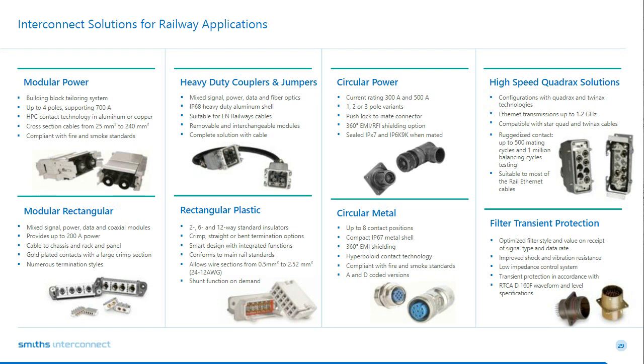Typically, why is it important to design a connection over 360 degrees? There are multiple reasons. First, by having a good EMC connection over 360 degrees, you're able to keep a more stable cable impedance, which helps avoid impedance mismatching. Second, by having a large surface of contact over 360 degrees, you can properly decrease the ground connection's contact resistance, so you can easily capture EMI perturbations and send them back to the ground.